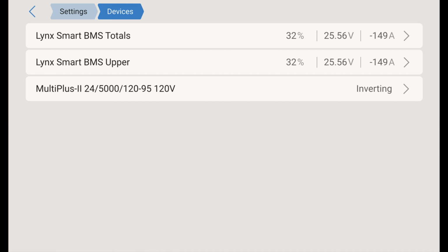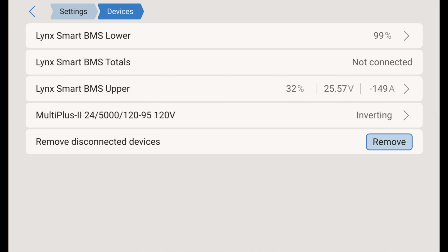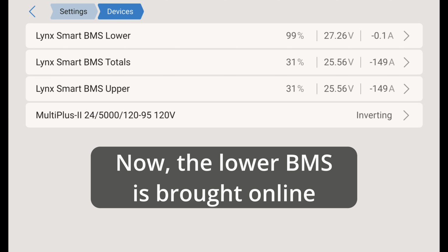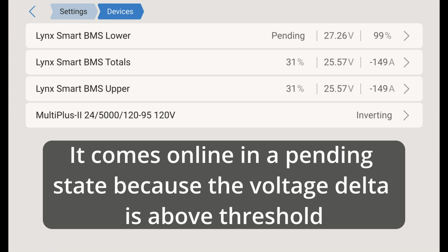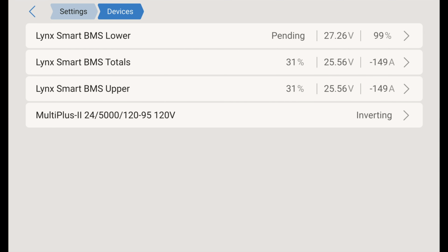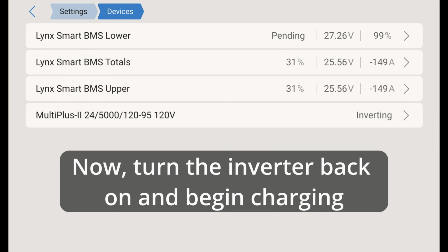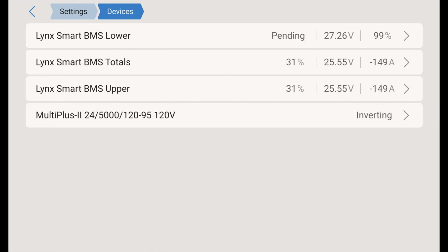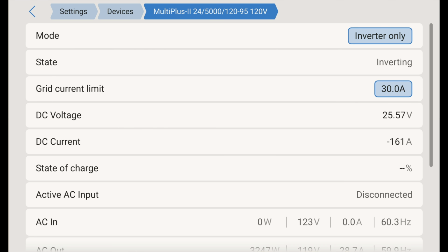What we'll see is that it will not immediately come into circuit because of the difference in voltage between the two. So we've just turned the lower BMS back on. You're going to see the pre-charge there, that negative 0.1 amps. Now that it's online, we see it is pending. That is because there's a relatively large difference between the voltage of the upper and lower batteries, about 1.7 volts.